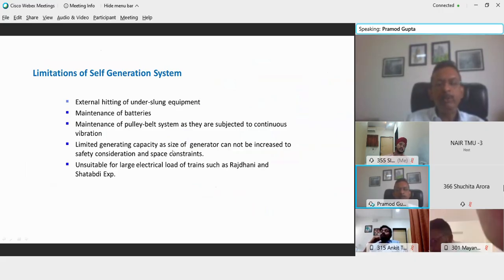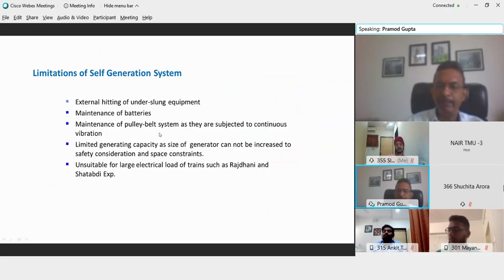The maintenance of the pulley belt system is also very tricky, because we have the mechanical component of the pulley and belts. The belts may get elongated during summer and have a weathering effect, becoming brittle after a certain period of service. Alignment between the pulley and belt is also very important - without adequate alignment, there will be continuous rubbing and local heating, causing the belts to melt and fall down.